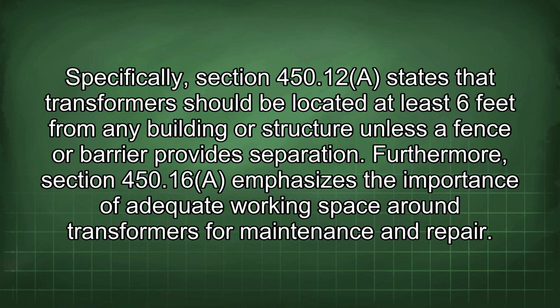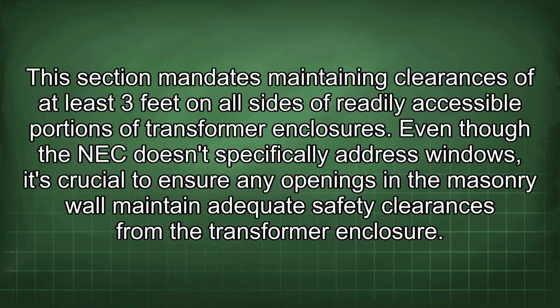Furthermore, Section 450.16 emphasizes the importance of adequate working space around transformers for maintenance and repair. This section mandates maintaining clearances of at least 3 feet on all sides of readily accessible portions of transformer enclosures. Even though the NEC doesn't specifically address windows, it's crucial to ensure any openings in the masonry wall maintain adequate safety clearances from the transformer enclosure.